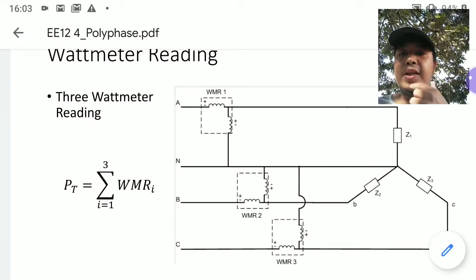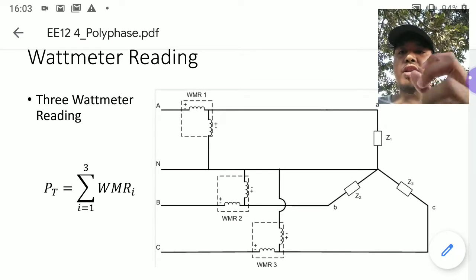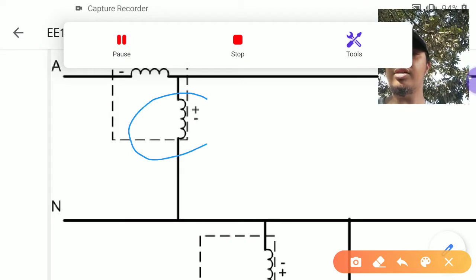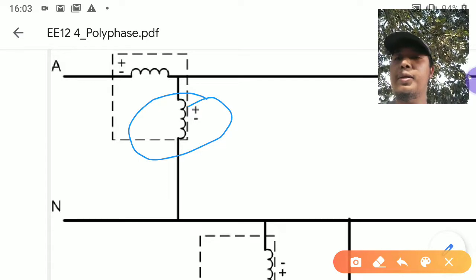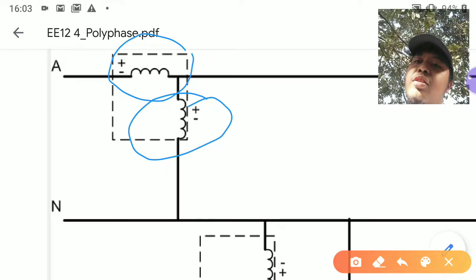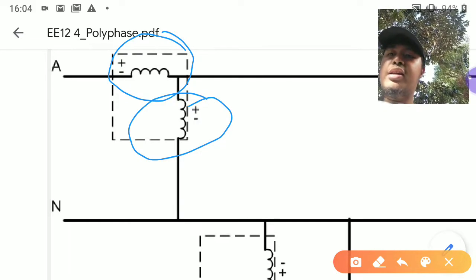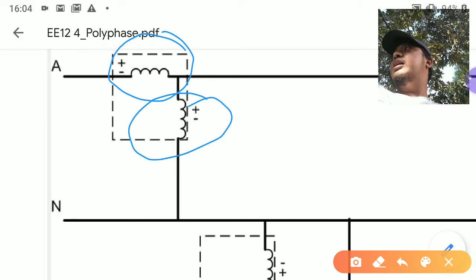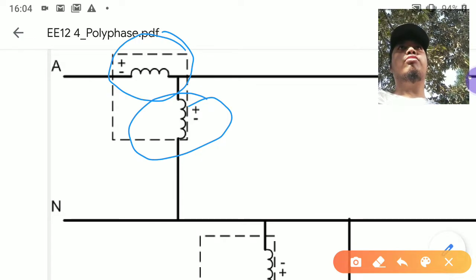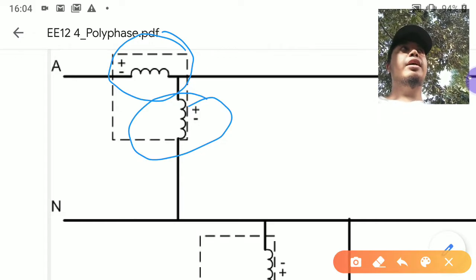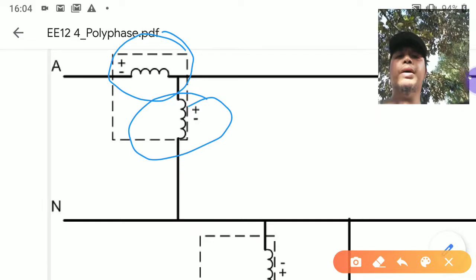For a four-wire Y system, this is actually easy. You can get the voltage at each phase by connecting a voltage coil between, say, phase A and neutral — that gives you the voltage at phase A. The current at each phase is measured with a current coil. You can do this for all phases, getting the voltage at phase A, B, and C, and the current at line A, B, and C — which, for Y systems, are the same as the phase currents. You then sum the power at each phase to get total power.